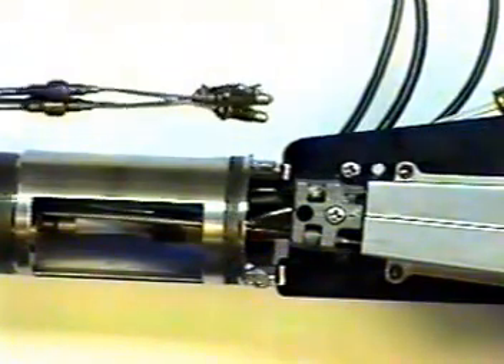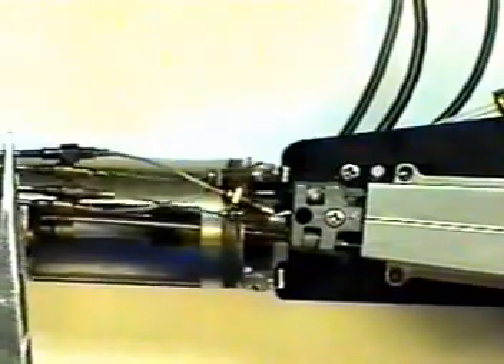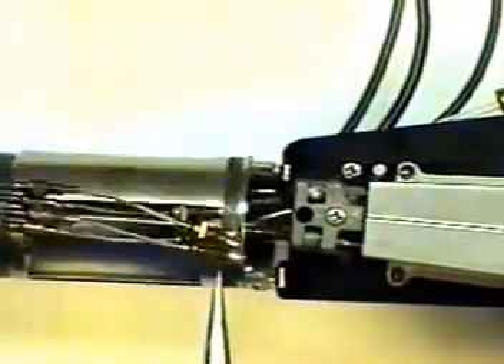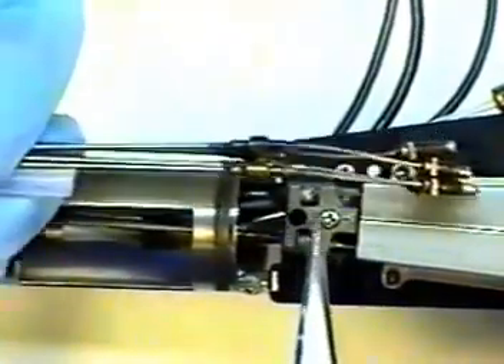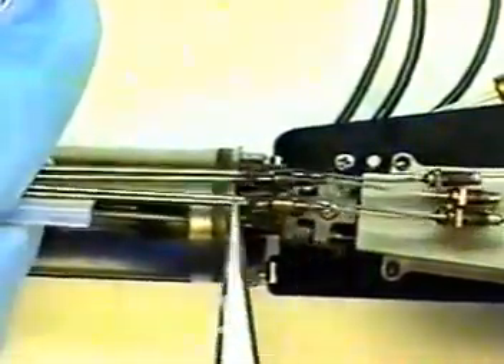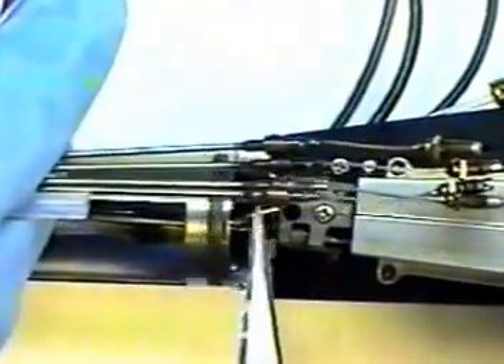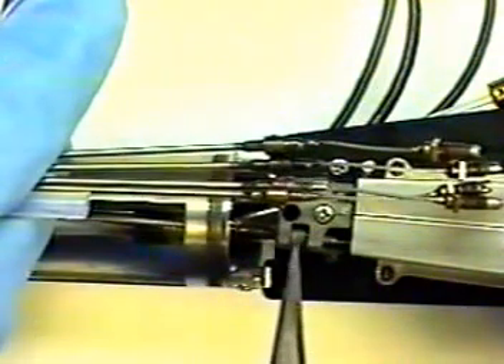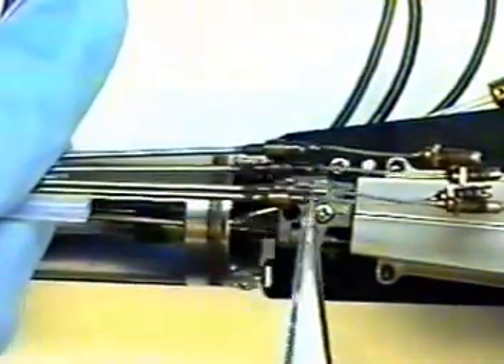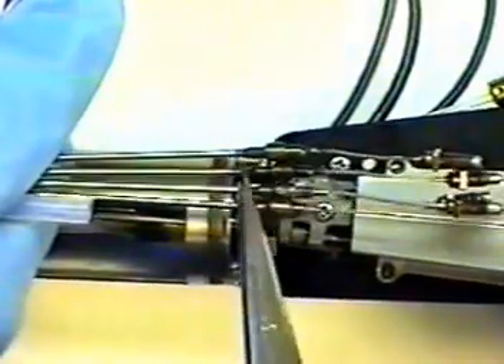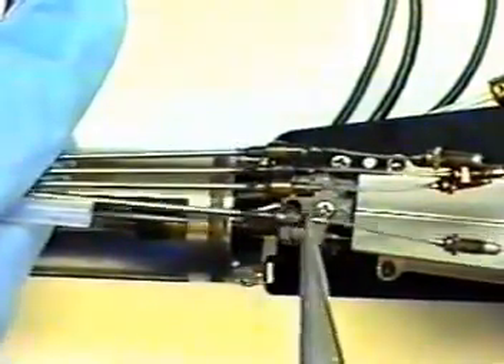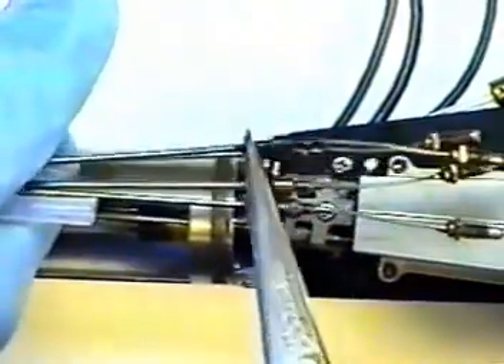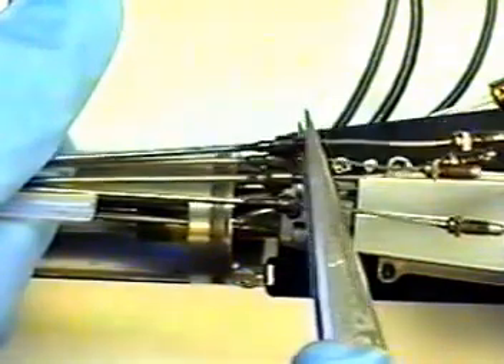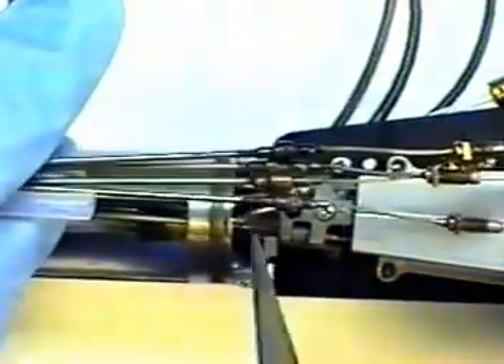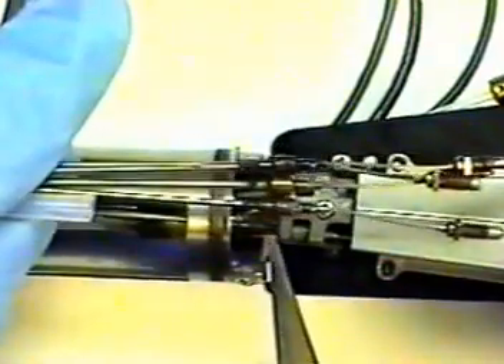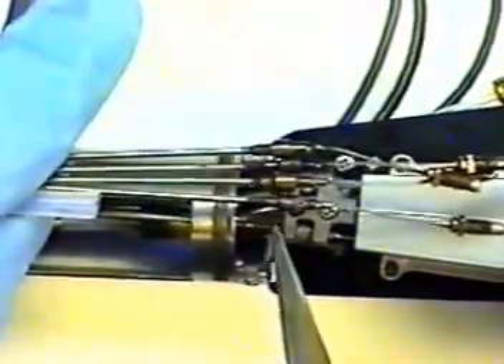Carefully turn over the instrument and pull through all 4 coil pipes, angulation wires. You need to reattach these into the angulation wire control block assembly. These coil pipes and angulation wires are color-coded from the factory. Color codes are as follows. The red marking on the coil pipe is for your up angulation. The black color coding is for your down angulation. Green is your left angulation cable, and silver or no color is your right.